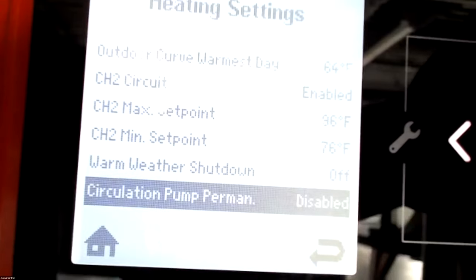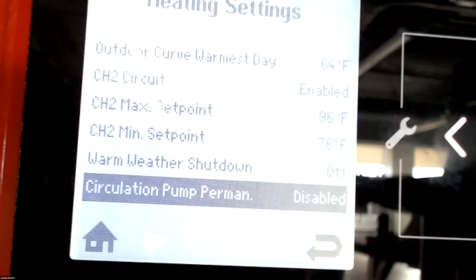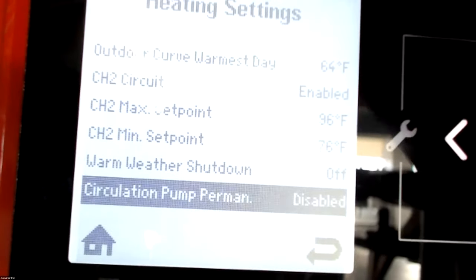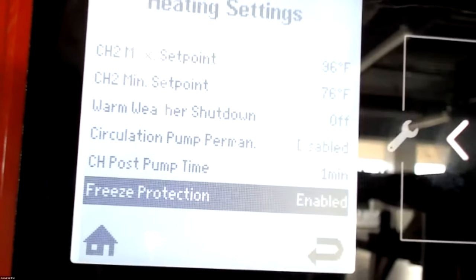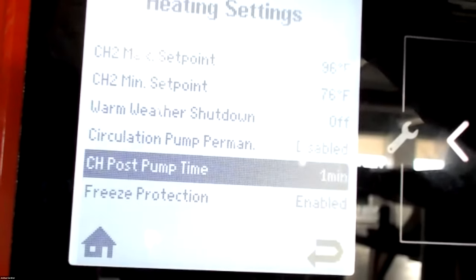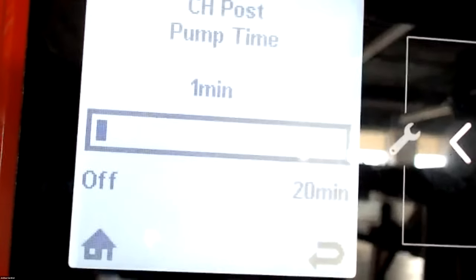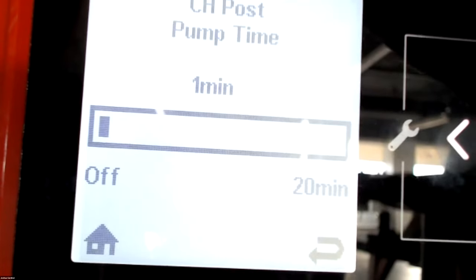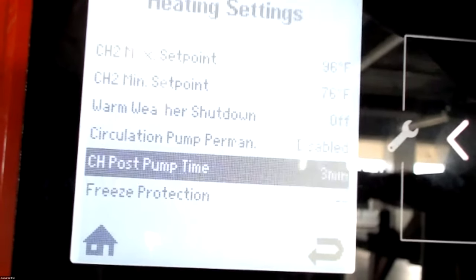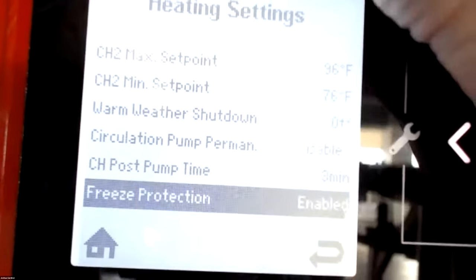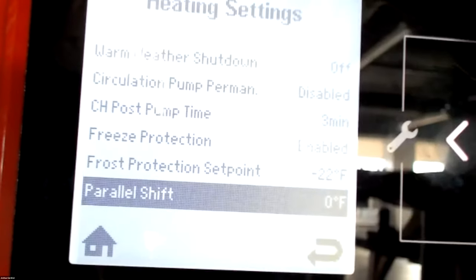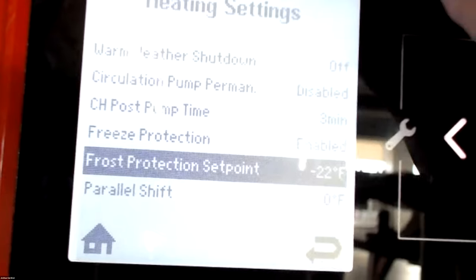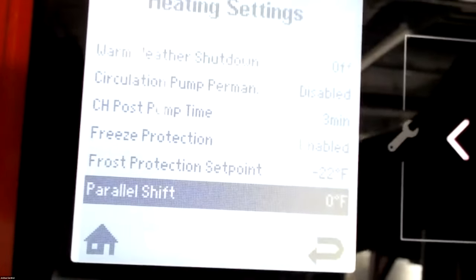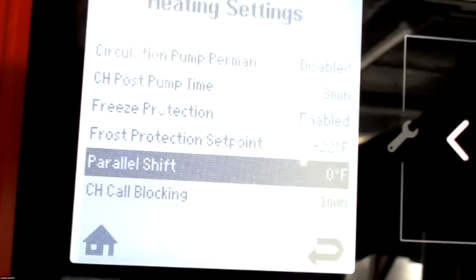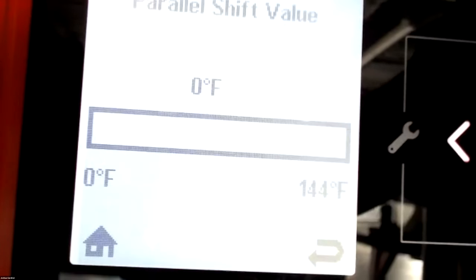And then warm weather shutdown. Our circulation pump, if we want to run permanent or only want to call, we can actually run permanent if you wanted to. Our post pump time to get that heat out of the boiler, put in our low loss header. If you're using a buffer, get that heat out of there. Maximize our efficiency, you can adjust that. Our freeze protection and frost protection come factory enabled, and frost protection comes set up. Our parallel shift, we're gonna have set from the factory at 0 degrees.